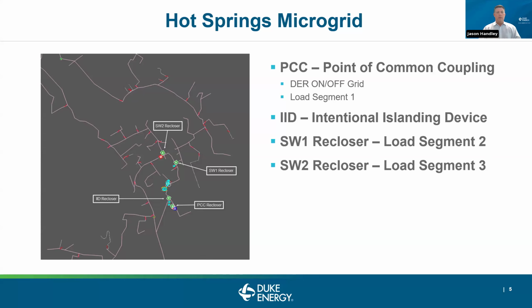And then you may see there we have what's called an IID, or an intentional islanding device. This is what allows us to separate completely from the upstream grid, going back to the substation. So we use that device first whenever we have to island. We will open that device if it's not open already, and then we'll close the PCC recloser.